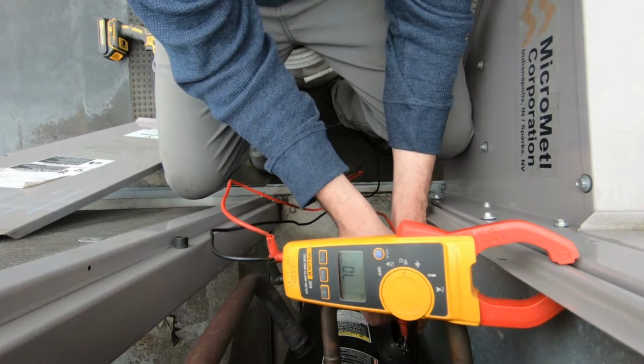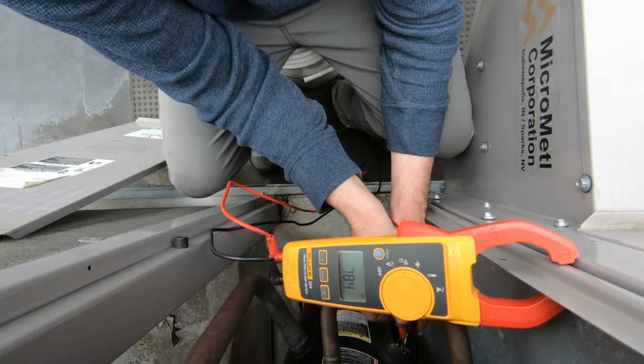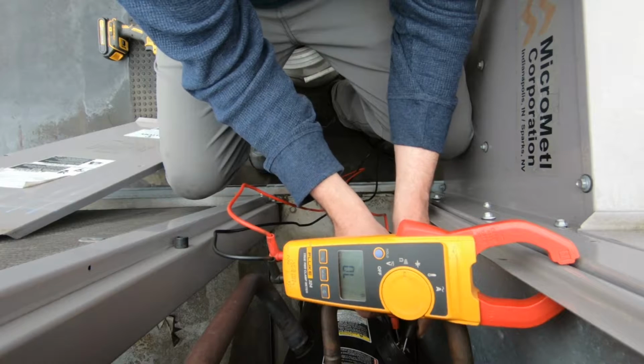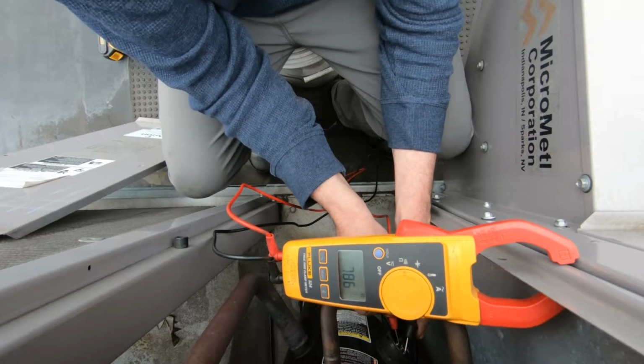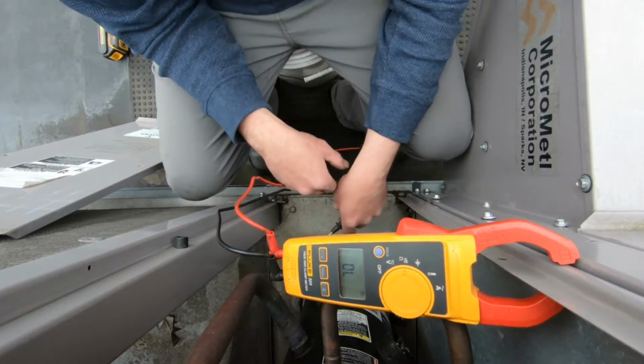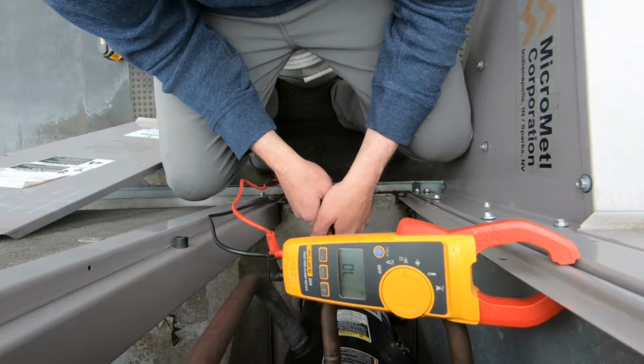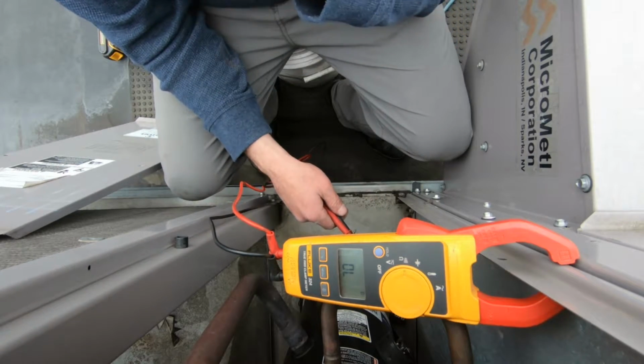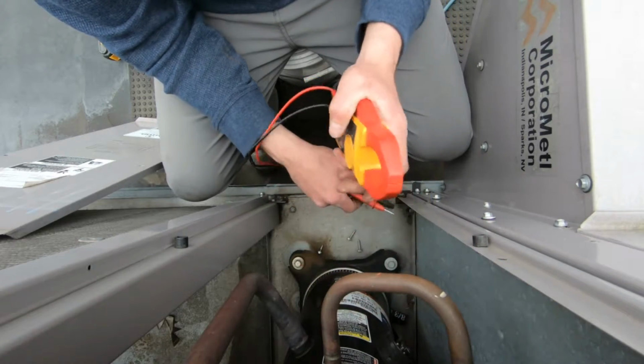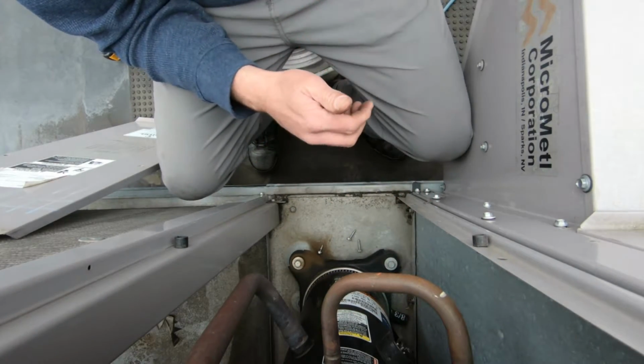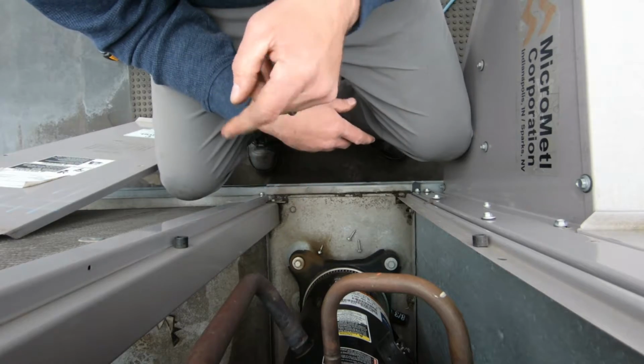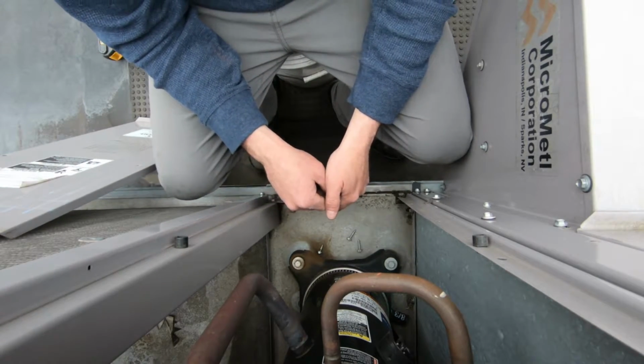So we got 5 ohms there, and we've got 784 there, and 786 there. So this compressor's shot. So we'll write up a new compressor, filter dryer, heat exchanger. This unit needs it all. Electrical repair, contactor, filters, compressor, the whole shebang. They might just want to replace this one.